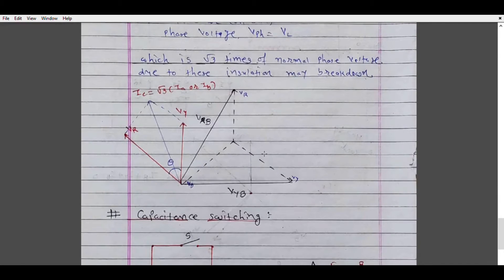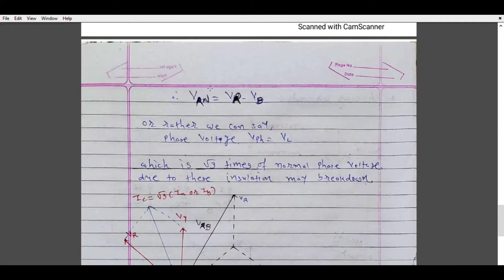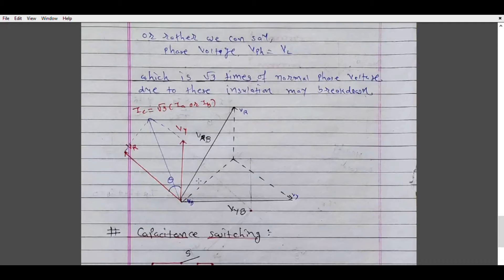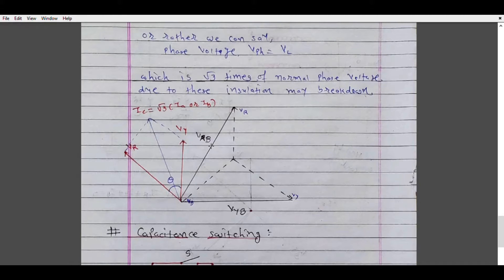Let us draw the vector diagram for this condition. In the healthy phase condition we have Vr, Vy, and Vb. To find VRB, which is Vr minus Vb, we do the vector sum and it gives us Vrb. Similarly we can find Vyb. The charging current in the R phase leads Vrb by 90 degrees, giving us Ir, and the charging current in the Y phase leads Vyb by 90 degrees, giving us Iy.